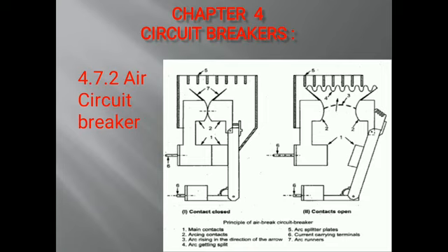Arcing contacts are used to relieve the main contact from damage due to arcing. Arcing contacts are easily renewable when required. During the opening of the main contact, there will not be any arcing in the main contact. The arc is only initiated after finally the arcing contacts are separated. These contacts close before and open after the main contact during operation.